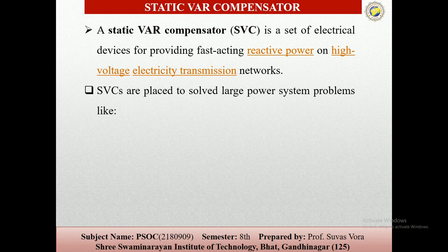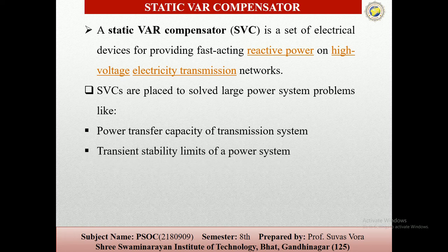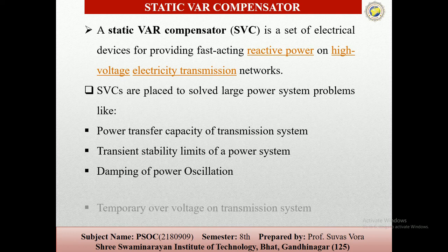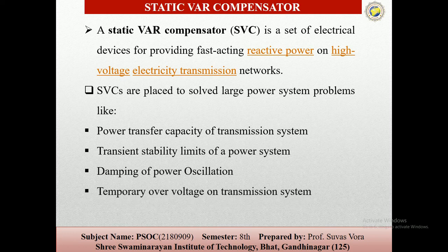So the static VAR compensators are placed to solve large power system problems like the power transfer capacity of the transmission systems, transient stability limits of the power systems, damping of the power oscillation, temporary voltage overvoltage of transmission systems, and damping of the subsynchronous oscillations.